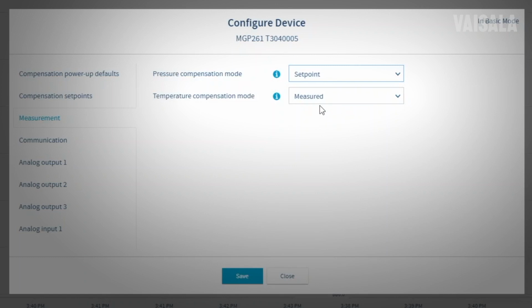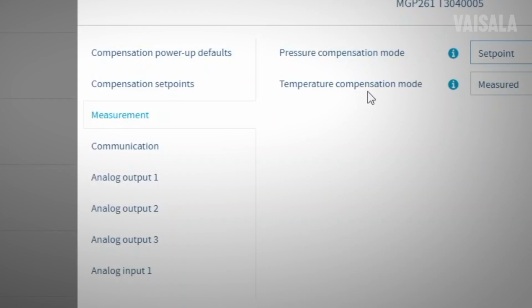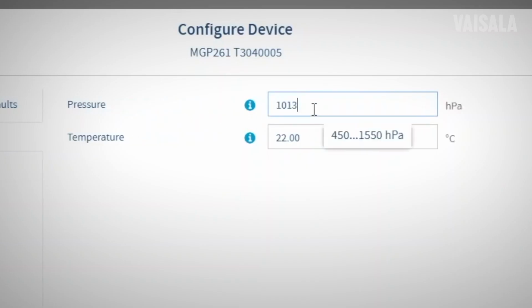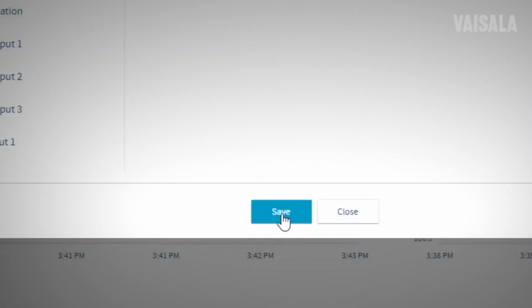For a fixed pressure set point, you'll select Set Point. From there, you'll enter your average operating pressure in hectopascals, which is the same value as millibars. From there, you'll press Save and exit the configuration menu.